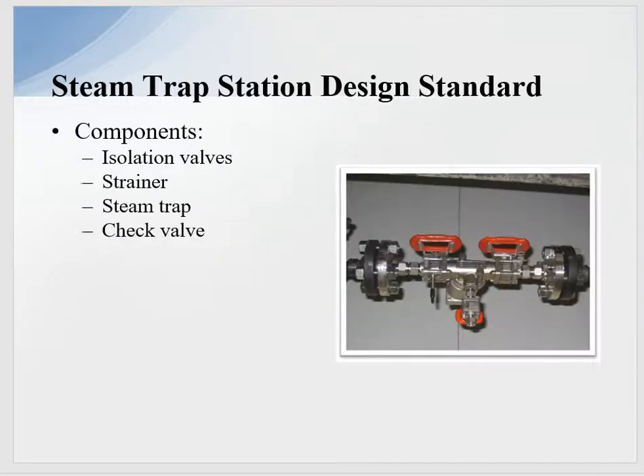One of the things I always talk to people about is steam trap station design standard. Have a standard for a steam trap station — don't just put in steam traps, put in steam trap stations. The station is made up of an isolation valve, strainer, steam trap, and check valve.